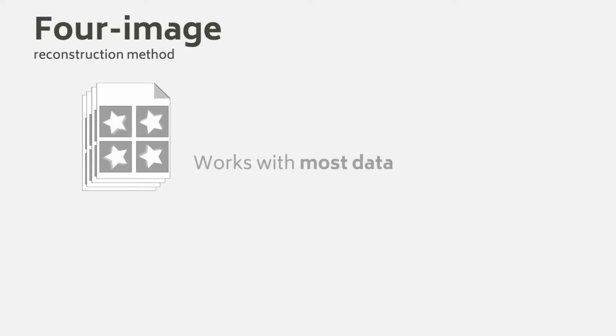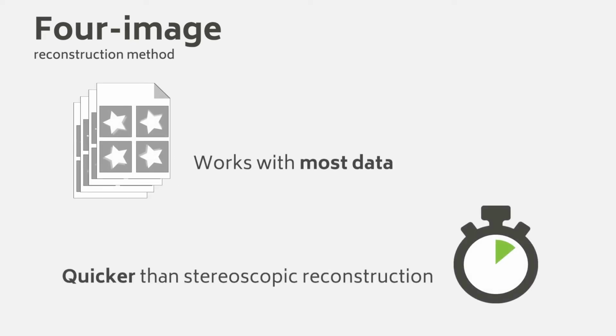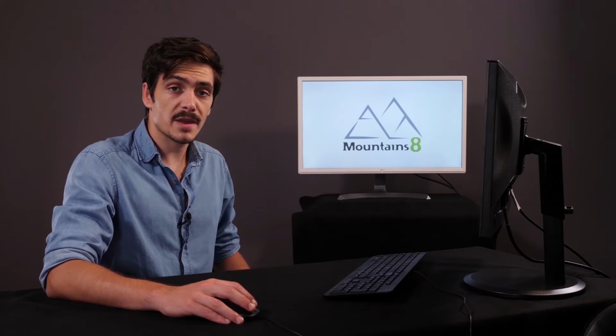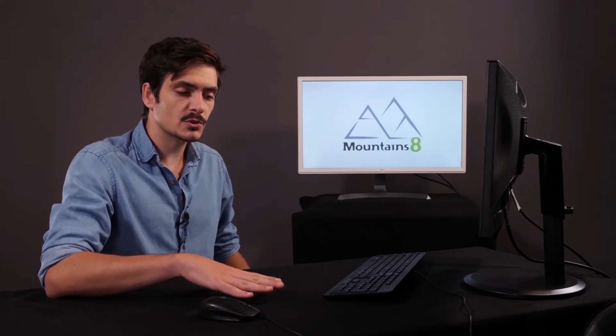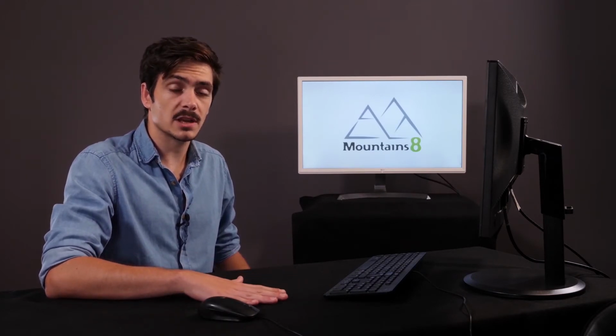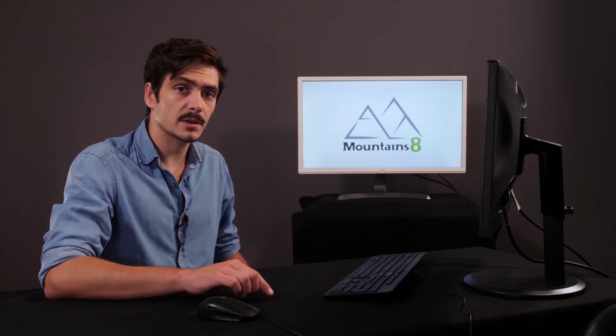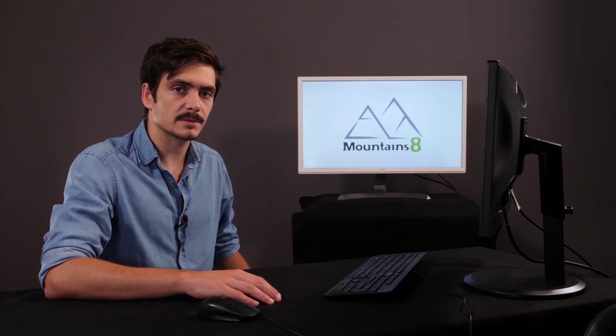The particularity of this reconstruction method is that it is greatly appreciated because it works with most data. Also, this technique is much quicker than the stereoscopic reconstruction, especially in terms of acquisition time. With this reconstruction method, you have to keep in mind that in order to get accurate results, metrologically speaking, you have to calibrate using a calibration standard provided by your instrument manufacturer.